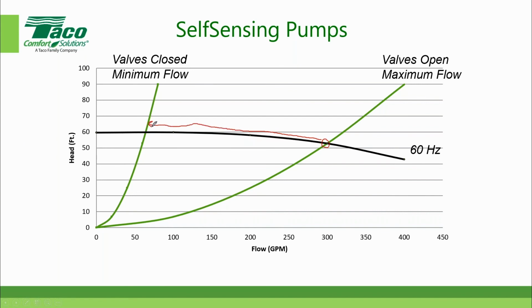system curve. And if it happens to be modulating control valves, you can think of it as almost being infinite in terms of the change. We know in reality it's not infinite, but it's fairly close. Okay, that would make the self-sensing pump relatively energy efficient, but I mean, you would save some energy, but it's not very energy efficient. So what would be nice is if we could change the speed at the same time we're changing the valve position.